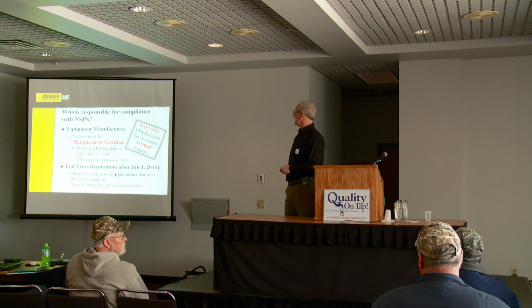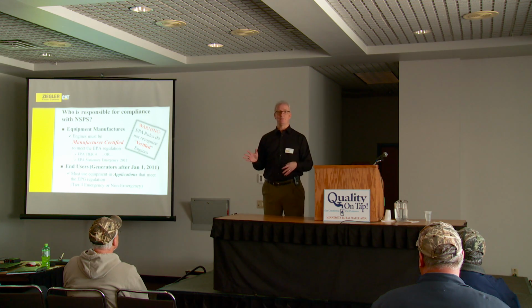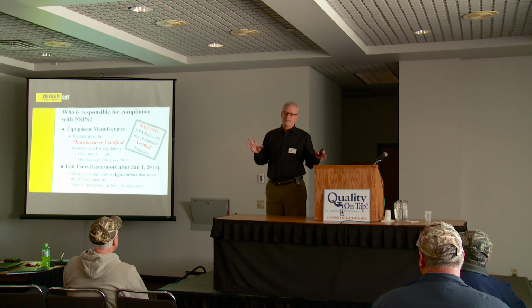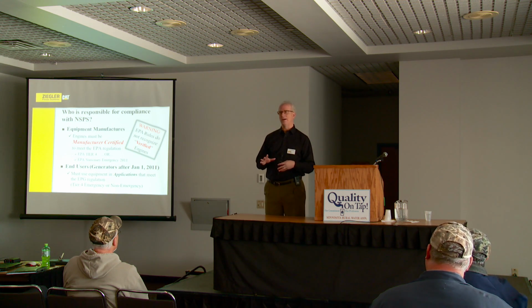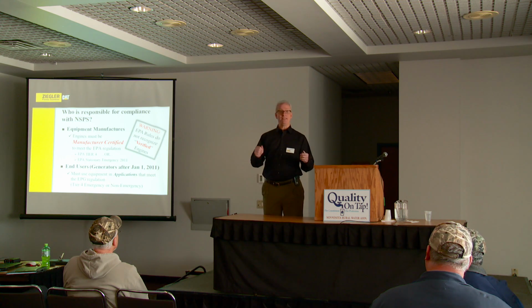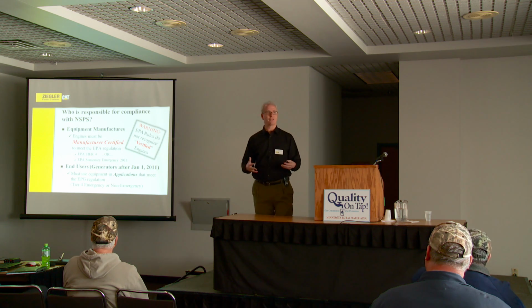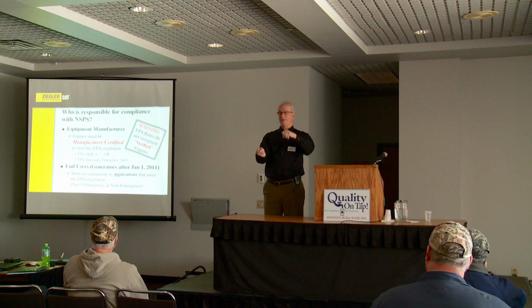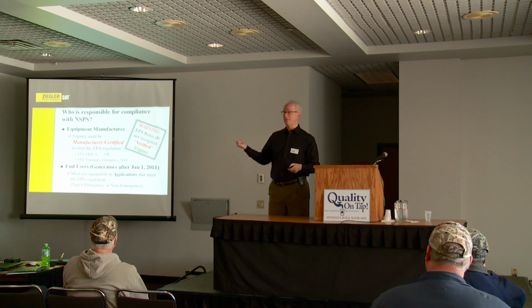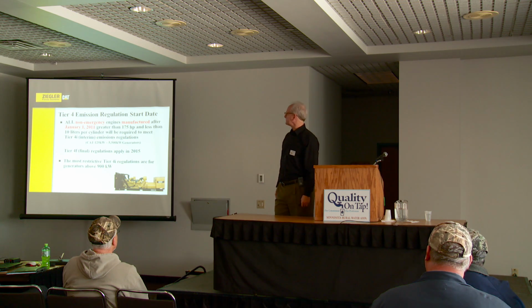So again, it's a discussion that happens and that didn't have to happen 2 years ago when you're talking about generators. The other thing I'd like to highlight, and I'll show you some pictures in a minute, is that the manufacturer has to certify these engines with the EPA. I've seen stuff where people say it says that this engine is verified to put out Tier 4 levels. Well, verified by who? Does it have an EPA certified sticker on it? Make sure that the things you're buying are not just verified, but actually certified by the EPA. So you can ask the manufacturer for an emission certificate and say, show me that it's EPA certified. Or you can look on the engines. I'll show you a picture here in a second, just some labeling on engines to highlight that.